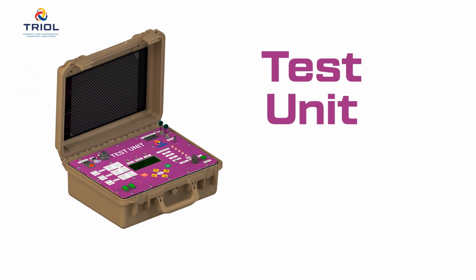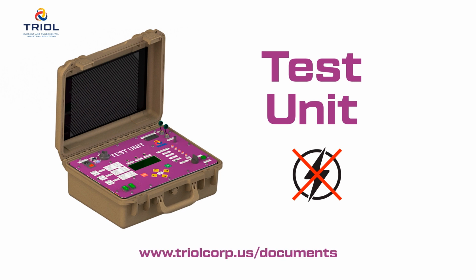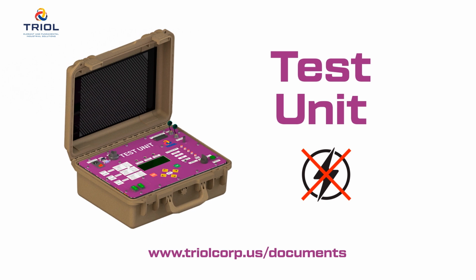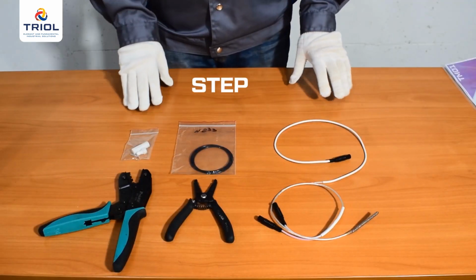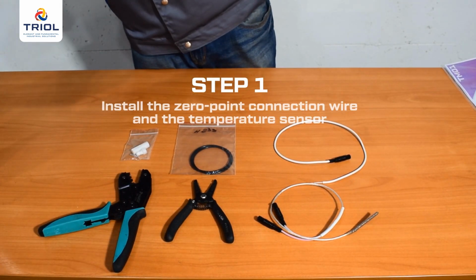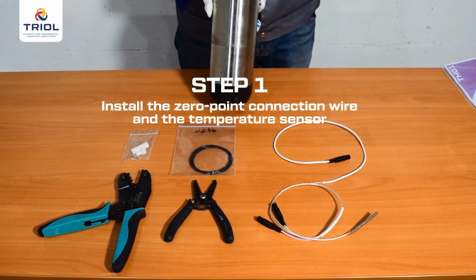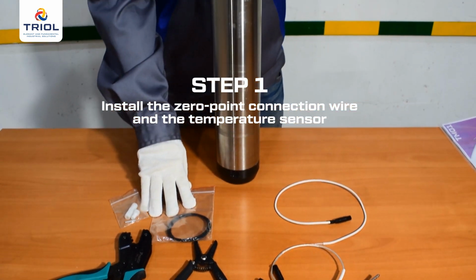You can also make a complete diagnosis of your sensor using the Triol test unit, the dedicated diagnostic tool. The test unit is self-powered, so you can check the connections without a power source. You can see the link for downloading a document describing the test unit on the screen. Test stand is ready. The instrument is ready. We can start. Step 1. Install the 0-point connection wire and install the temperature sensor in its proper place on the corresponding plug connectors.